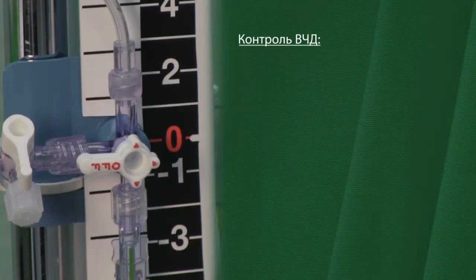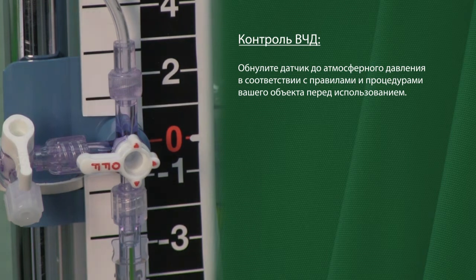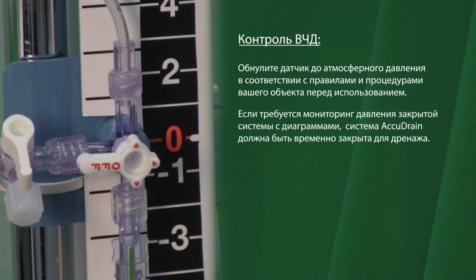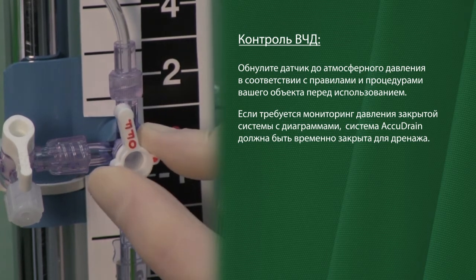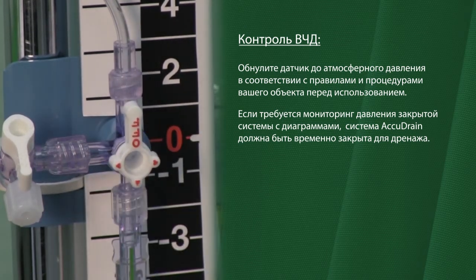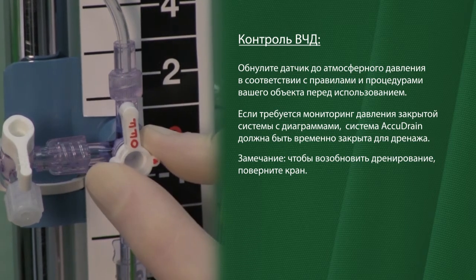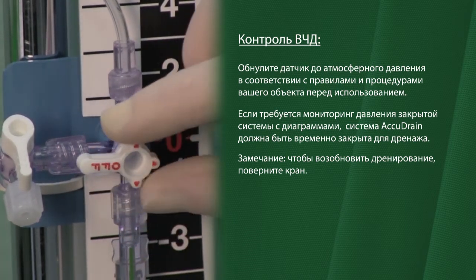Monitoring intracranial pressure. Zero the transducer to atmosphere per your facility's policies and procedures before use. If closed system pressure monitoring and waveforms are desired, the ACCUDRAIN system should be temporarily closed to drainage. Note: reorient stopcock to resume drainage.